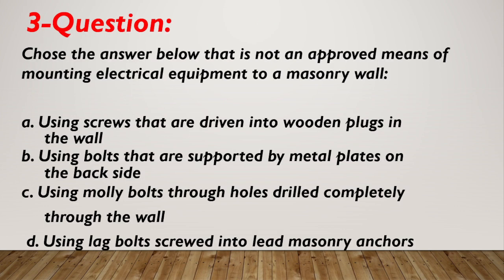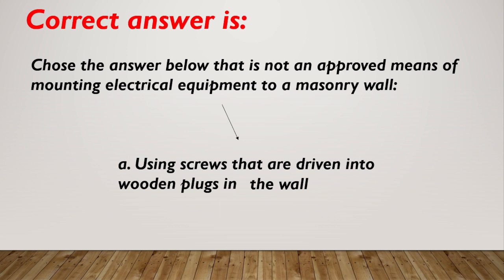Question number 3. Choose the answer below that is not an approved means of mounting electrical equipment to a masonry wall. A. Using screws that are driven into wooden plugs in the wall. B. Using bolts that are supported by metal plates on the back side. C. Using molly bolts through holes drilled completely through the wall. D. Using lag bolts screwed into lead masonry anchors. Correct answer is A: using screws that are driven into wooden plugs in the wall.